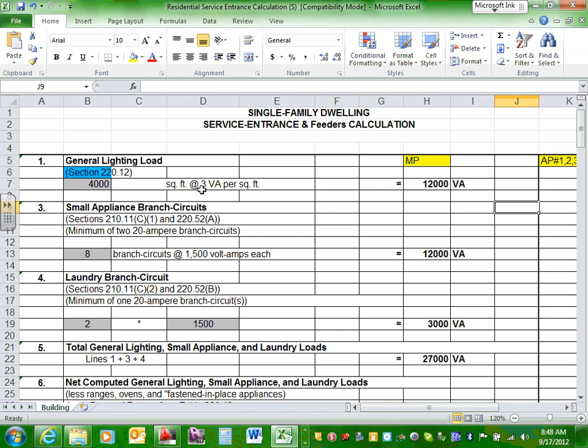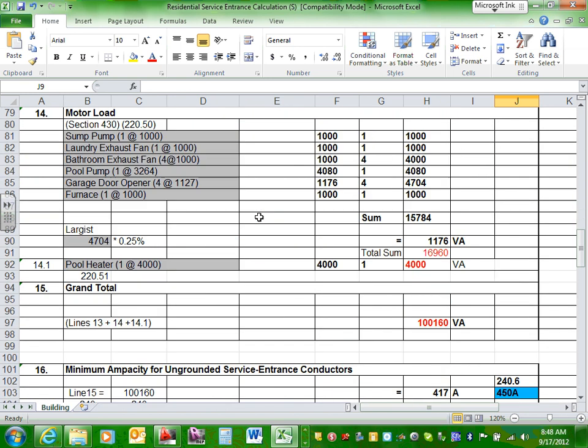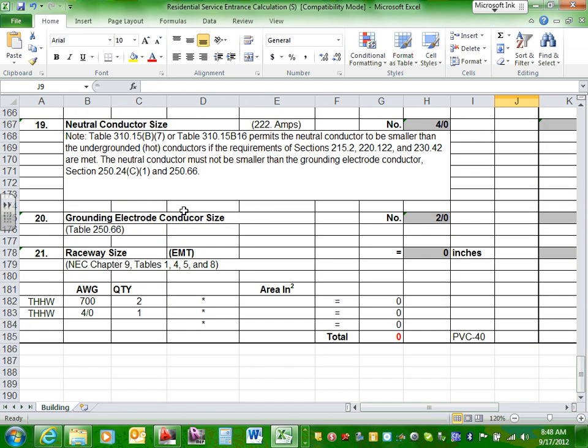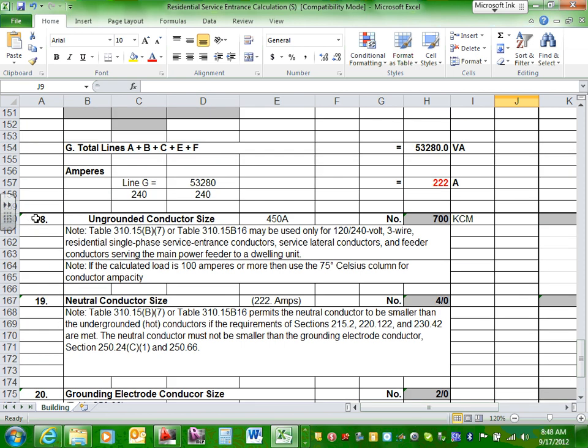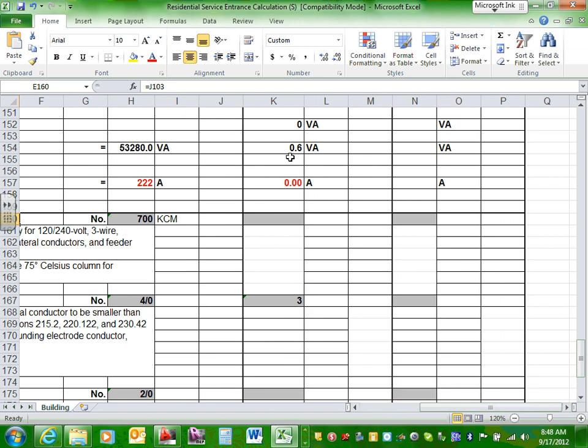Okay. Let me show you the outcome, by the way, because I always like to start at the end. Why are we doing this? If you go all the way down, here's why we're doing it, guys. At the bottom line, I need to size the ungrounded conductor, step 18, the conductor that's coming to this building, and I need to find the amp size of this building. That's what the bottom line is. And the same thing for apartment one, for the apartments, as well as for the common area. I'm not sizing it because you guys are going to come up with it. That's what we're doing, to come up with the overcurrent protection device for every apartment and the feeder that's going to the whole building. Everybody knows what the outcome is?